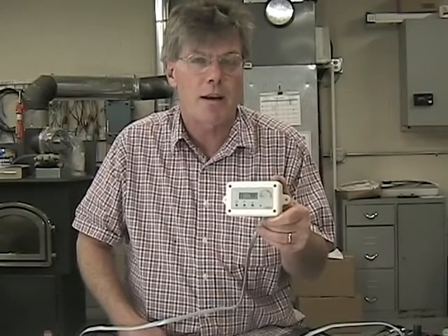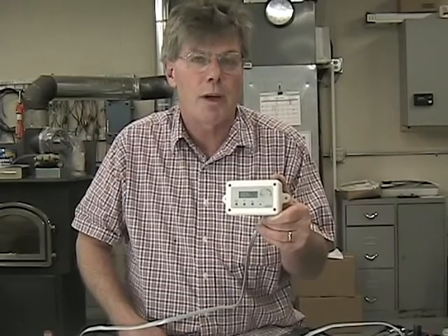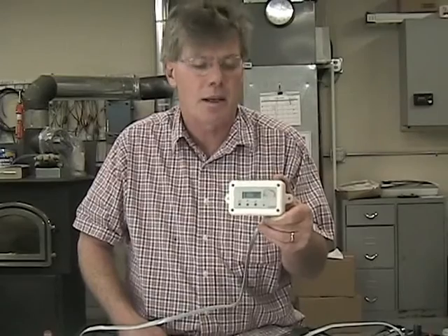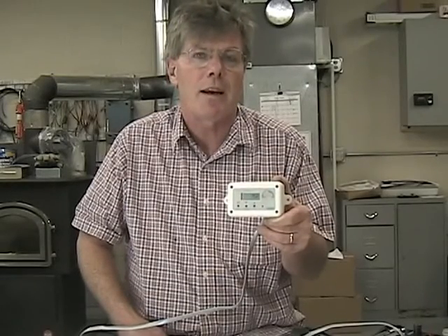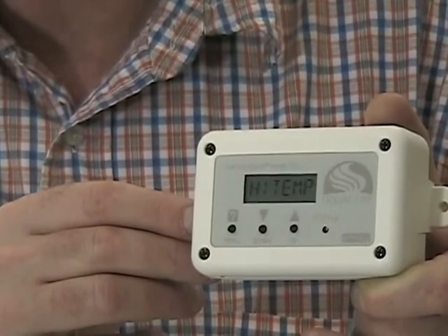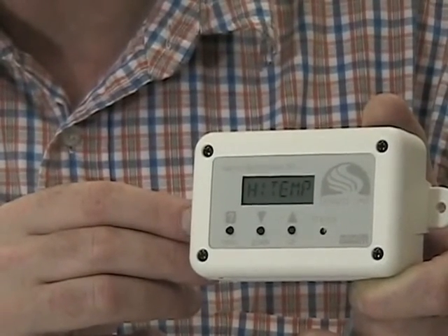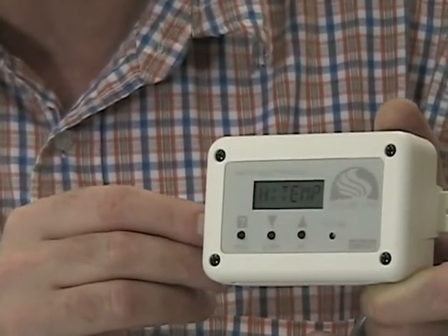One of the safety features of the Coal-trol thermostat is a mode where if the room temperature sensed by the thermostat exceeds 98 degrees, your stove will stop feeding and it will shut down, and the fire will go out. Once the high temperature indicates on the display, to reset this and go back to normal operation, two things must occur.